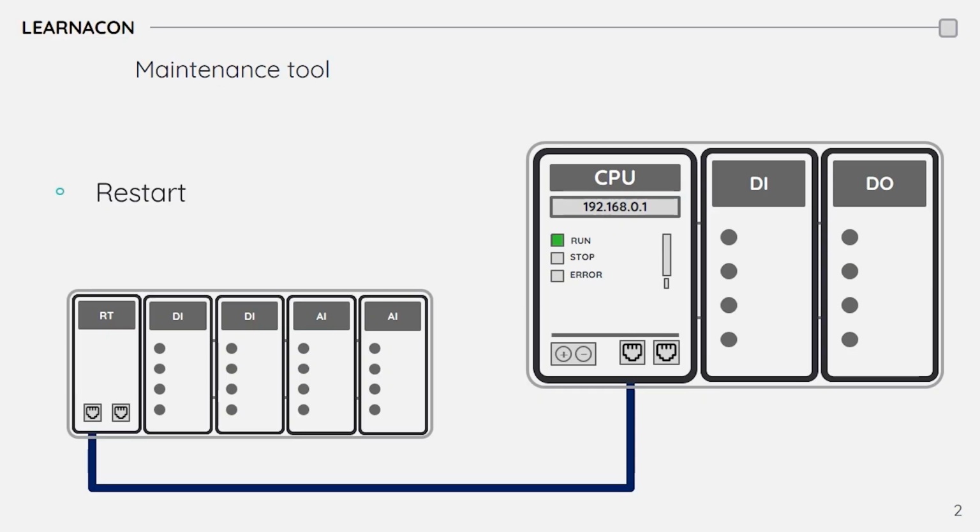The other maintenance function that you need to try once in a while is reset. This is a function that you have to do very carefully. A reset returns the CPU to the factory setting. It erases the program memory and even clears settings like the IP address. So before activating a reset function, it is reasonable to make sure that there is a working backup of the application program. After resetting a CPU, to get the PLC running, you need to download the whole configuration and program again.